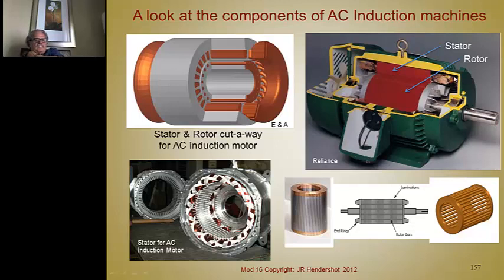But these fan blades here, all they do is circulate the air inside of the end turns here to cause the air in there to not cavitate against a smooth surface, but to be thrown out by these centrifugal blades against the end turns, and that in turn throws them out here to the surface of this aluminum end cap. Sometimes you even have fins on those, and so that circulation of the air gets cooled by its contact with the end ring. It's not real effective, but it helps. It works.